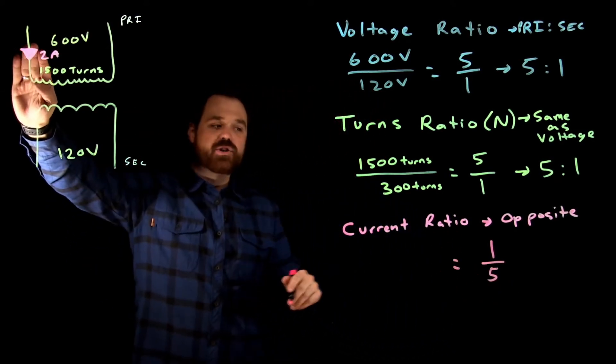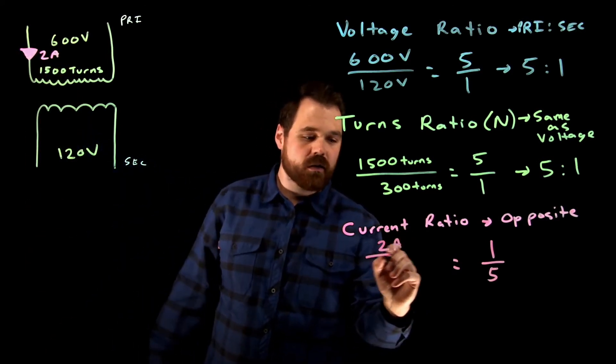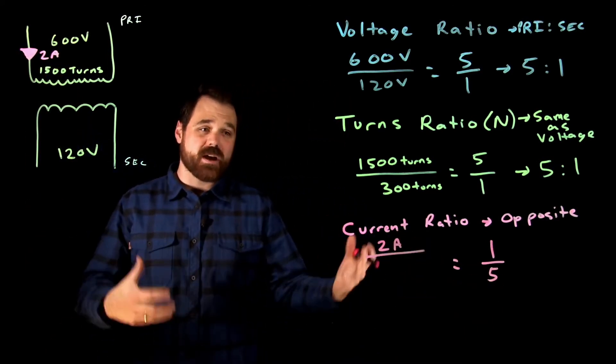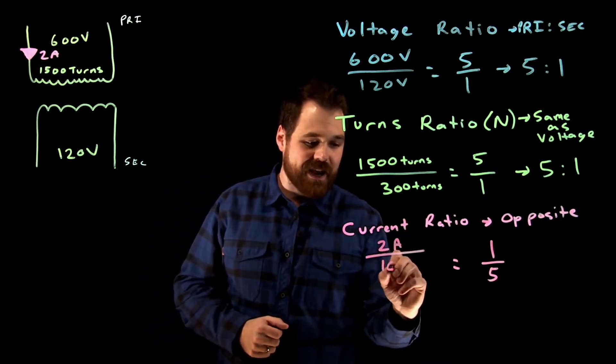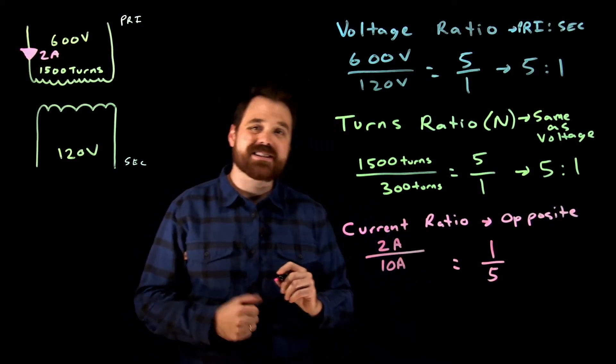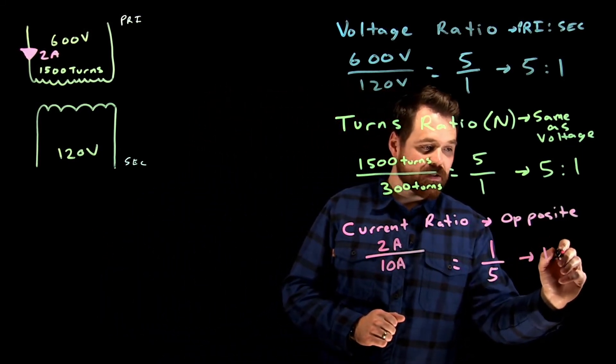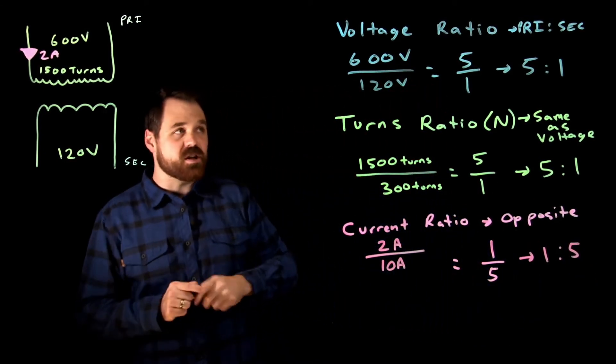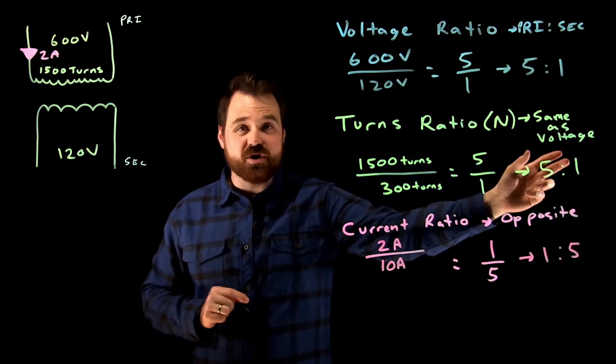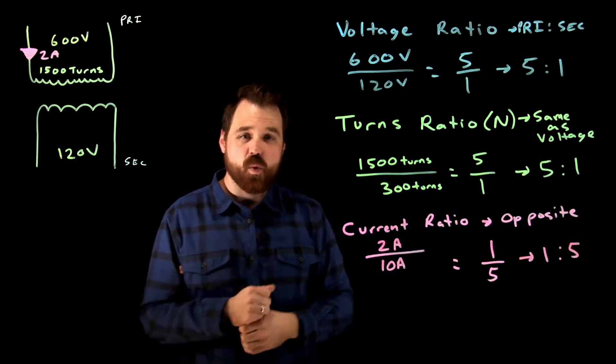So if we know we have two amps on the primary, we again would cross multiply, do a little transposing, two amps times five would give us 10 amps on the secondary. So in this case, we would have a one to five current ratio. So we can see voltage and turns are the same. The current is the opposite or the inverse of that. So it's a one to five.